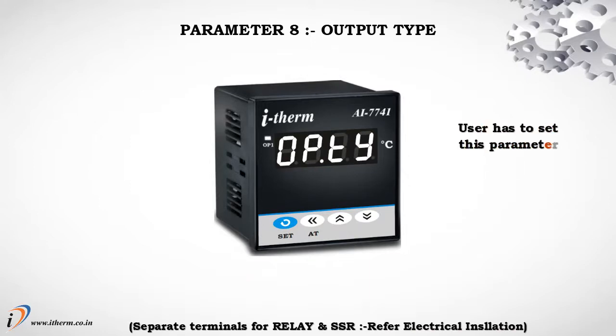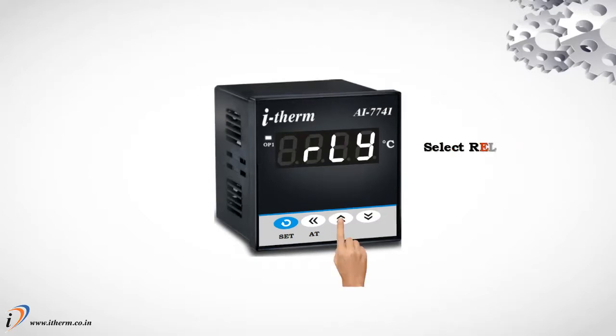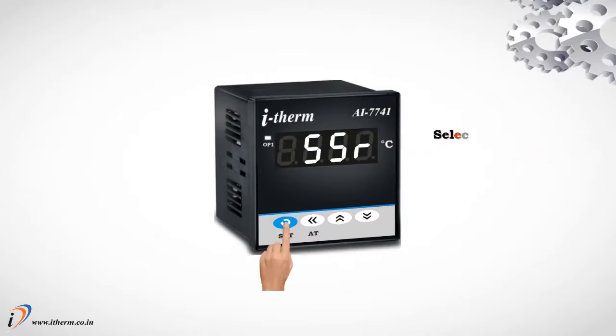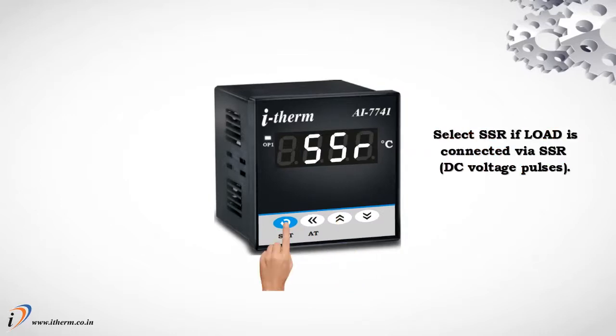Parameter 8. Output type. User has to set this parameter very carefully in accordance with the output used. Select relay if load is connected via contactor. Select SSR if load is connected via SSR.